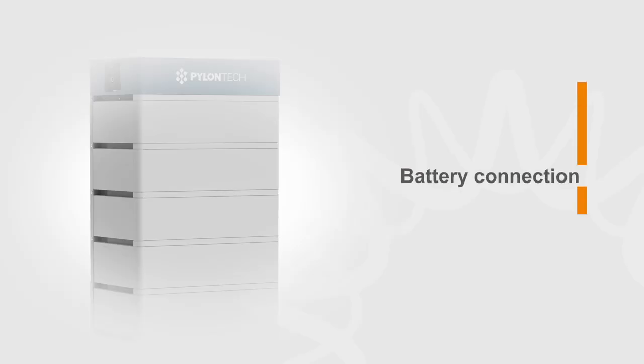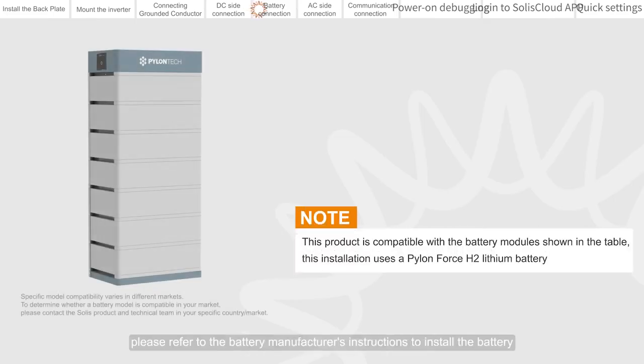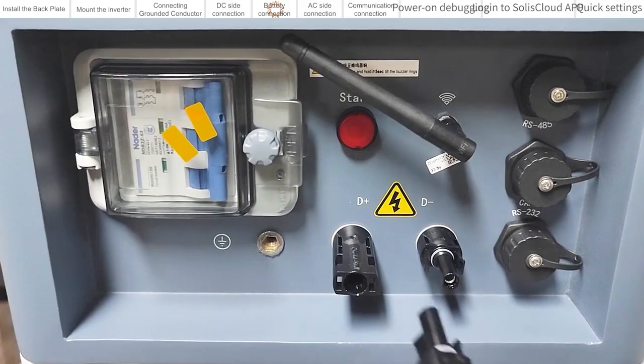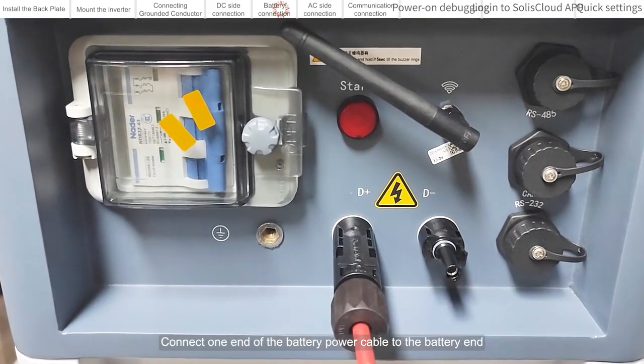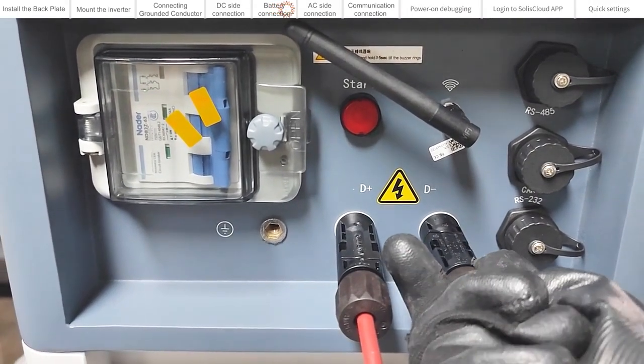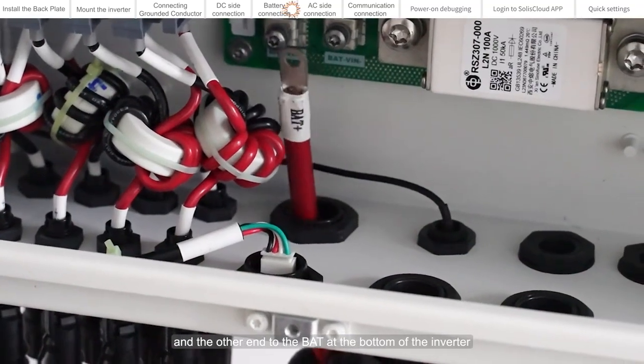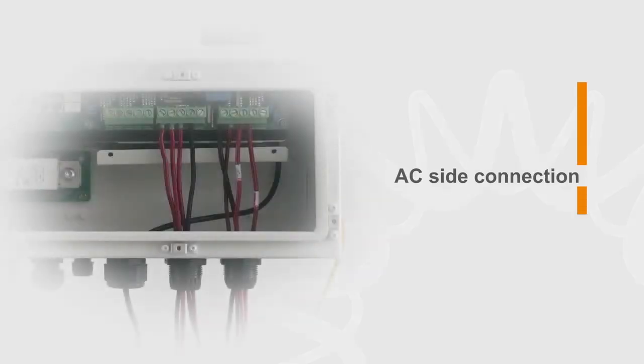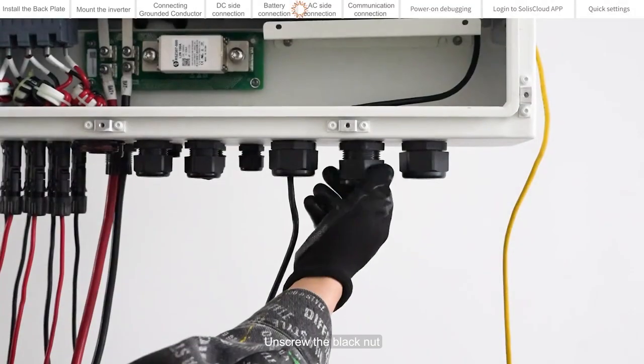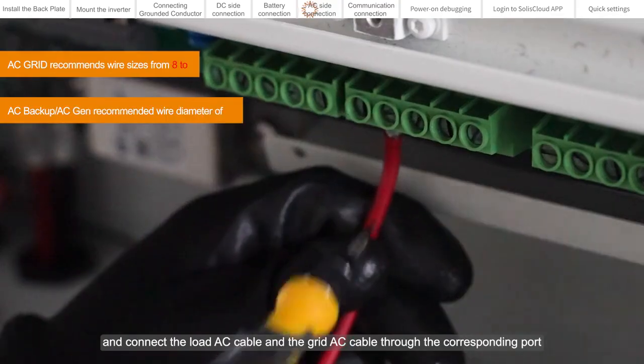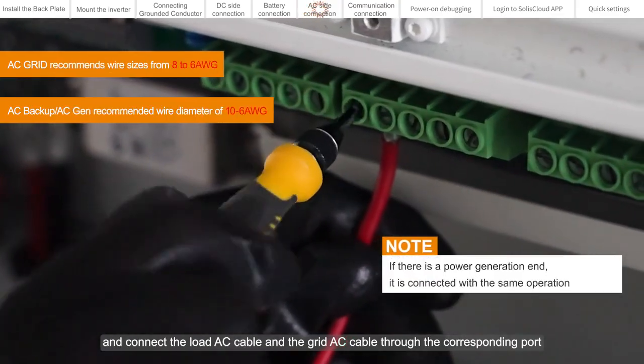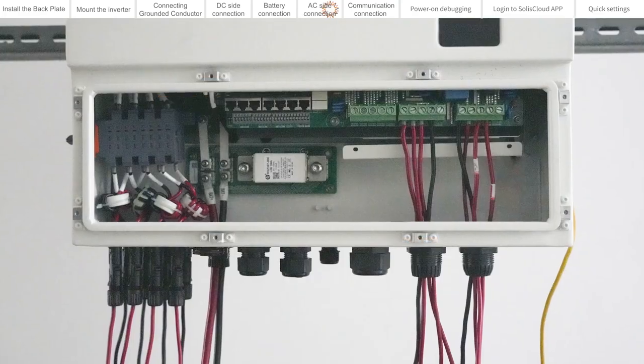Battery connection. For battery installation, please refer to the battery manufacturer's instructions to install the battery. Connect one end of the battery power cable to the battery end and the other end to the BAT at the bottom of the inverter. AC side connection. Unscrew the black nut and connect the load AC cable and the grid AC cable through the corresponding port to the corresponding terminal.